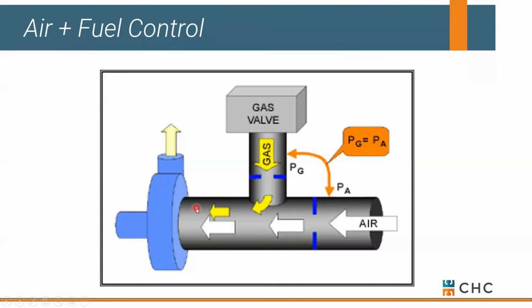So if we're taking our boiler up to 100% fire, the blower ramps up, we bring in more air. As we're doing that, we get a higher differential across this orifice, and the gas valve says, oh, I need to open up and allow more gas to flow in. As we get close to set point and our boiler modulates down, okay, less air. As we slow our air down, this gas valve also goes closed or starts to modulate down because we have less pressure difference. So the gas valve's along for the ride as the blower modulates up or down. That's how we get good combustion throughout full modulation. So typically you check this at low fire and at high fire to make sure that combustion properties are right. And after that, the gas valve simply tracks, how do I say it, the burner modulation, okay?